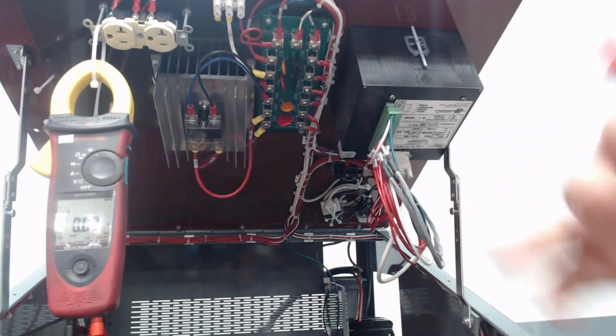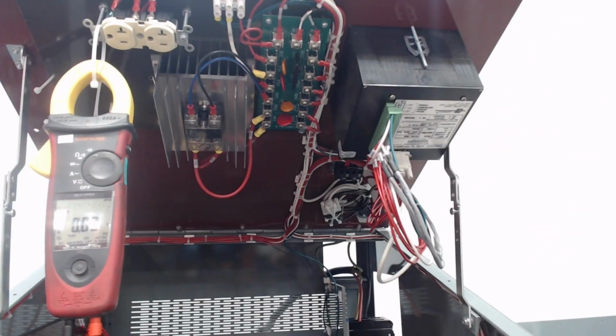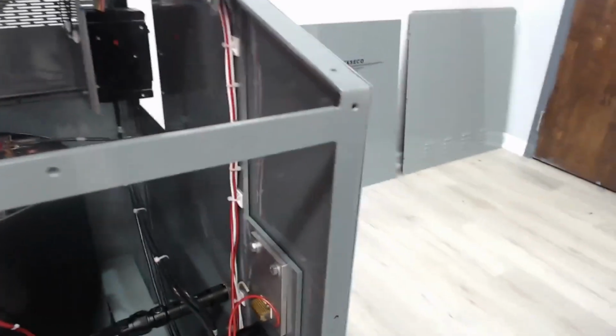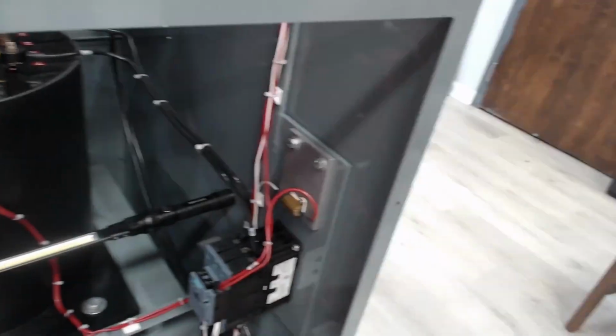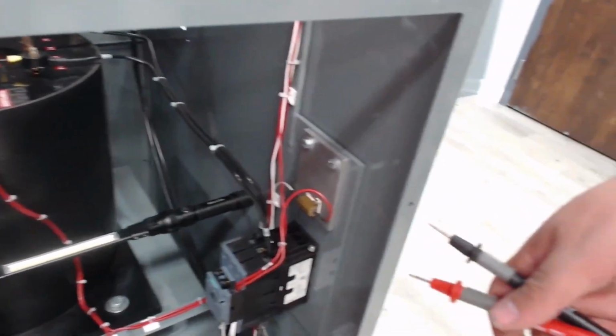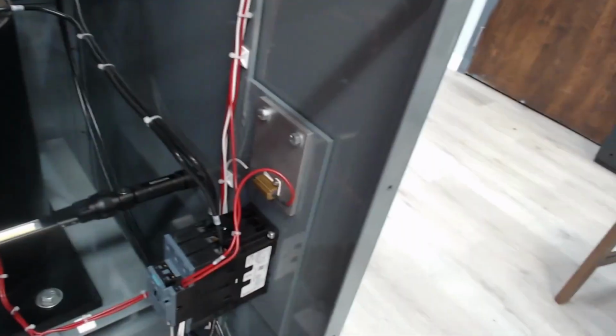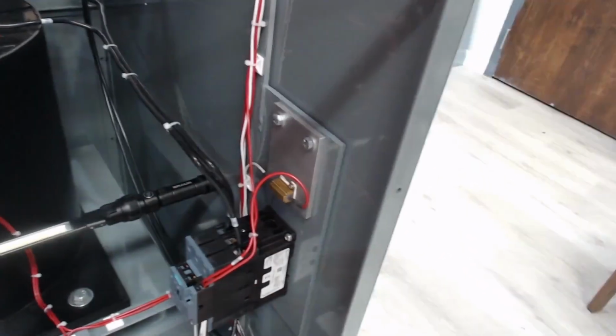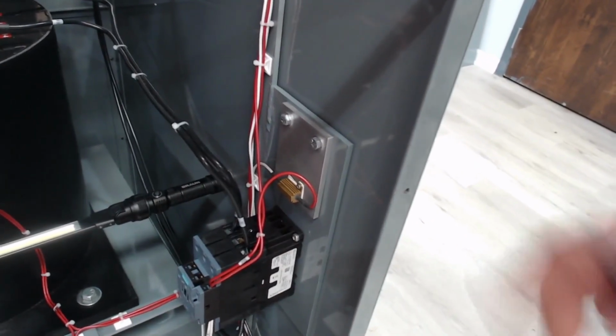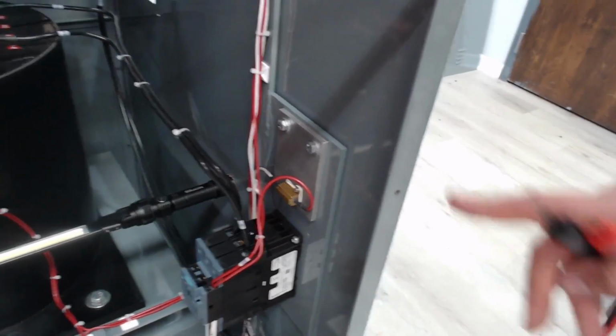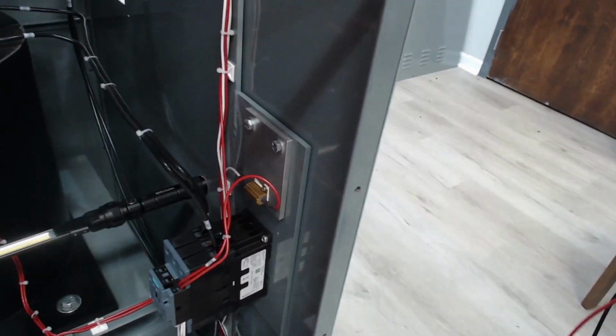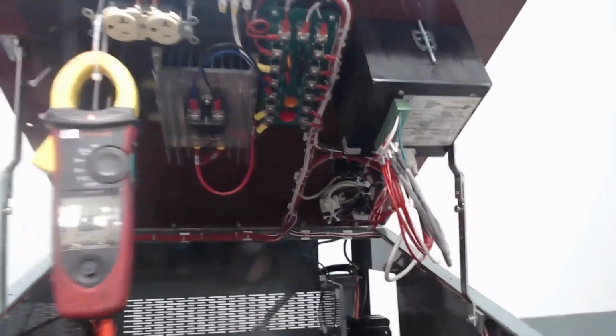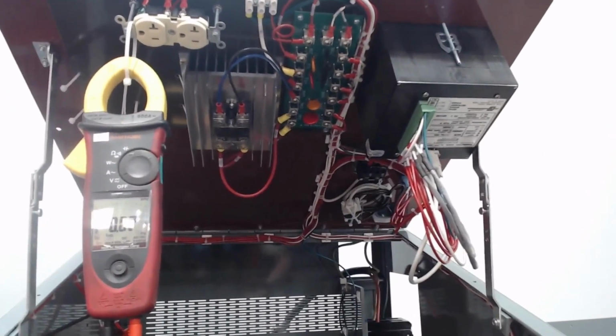So at that point, your contactor should be coming on. If not, then you might need to look at your actual contactor. So your actual contactor down here, you want to check and make sure you've got your 120 volts coming out onto the on power and it's just not a connection problem, or that contactor may need to be replaced. We do put a resistor because new contactors don't have much of a load and it's causing dropout. So that may be a thing too you want to look into.